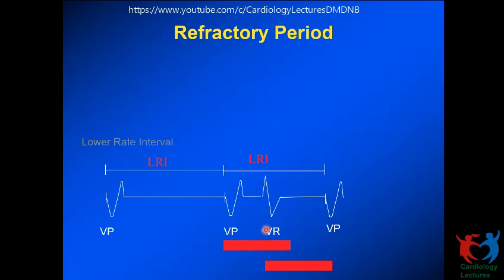Here, because it's falling in the refractory period, it's not going to reset the lower rate clock. But had it happened outside, it would reset the lower rate clock. Another point that you would want to remember is, if there is a refractory ventricular sense just like this, it would start one more refractory period, even though it did not reset the lower rate clock. By this time, the lower rate clock timed out and delivered a V pace here. So that's the little disadvantage of a longer refractory period.